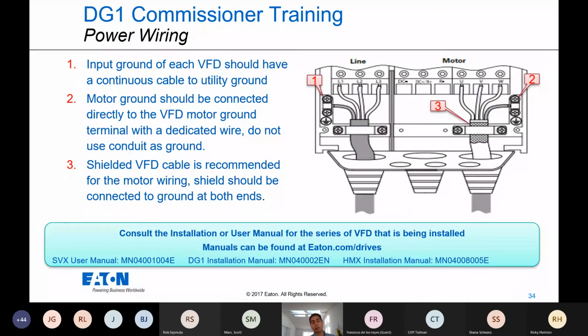And we did talk about motor line lengths. So if you have, let's say, an inverter duty motor and inverter duty cable, you have more leniency as to not necessarily having to have a long line length filter on the outputs.